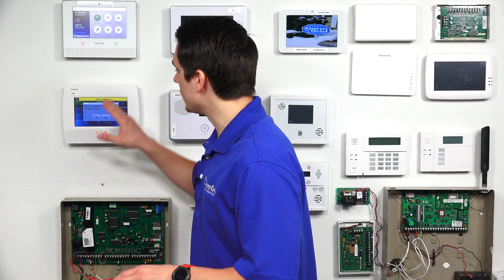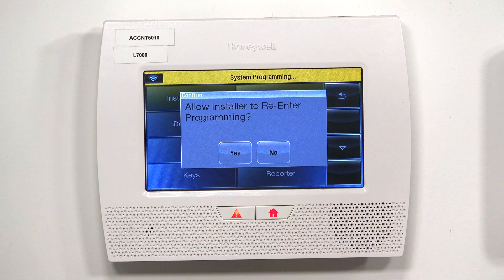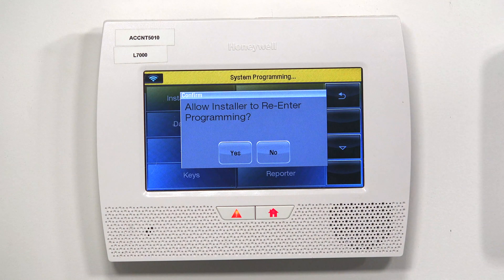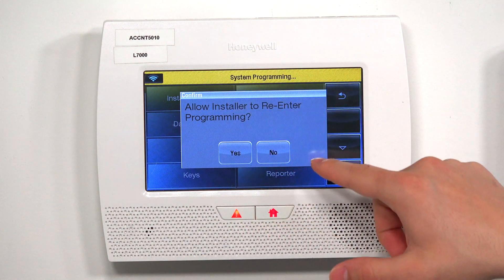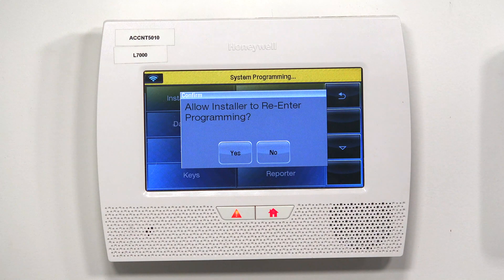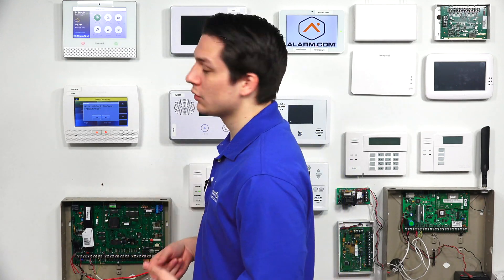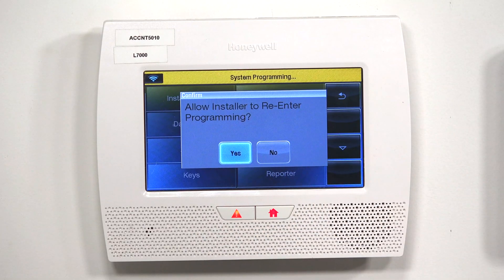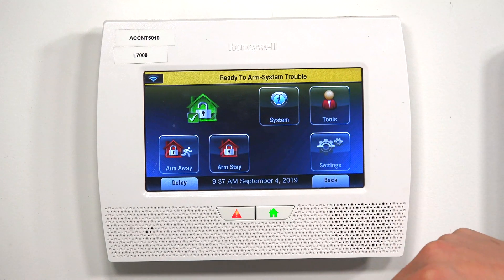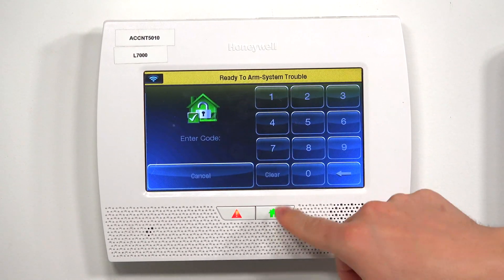For the Lynx Touch panel, when you're exiting out of the main menu, you do get a window that the Lyric does not give you. This little window asks whether to Allow Install to Re-Enter Programming — always press Yes. If you press No, you're going to be locked out of programming and will have to backdoor to get back in. So to avoid that, just press Yes, then hit the back arrow to return to the main screen.